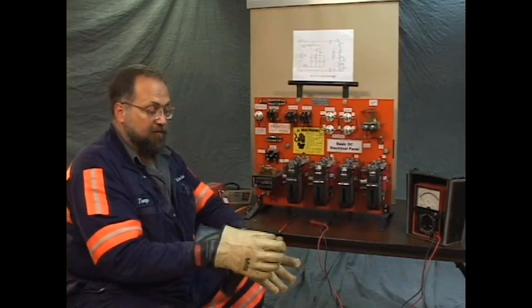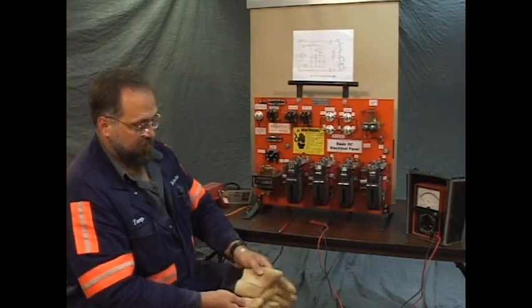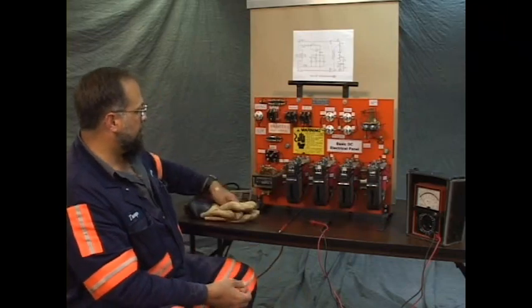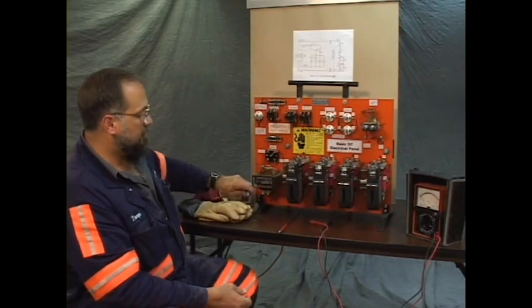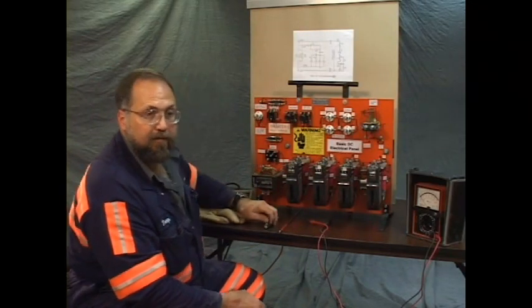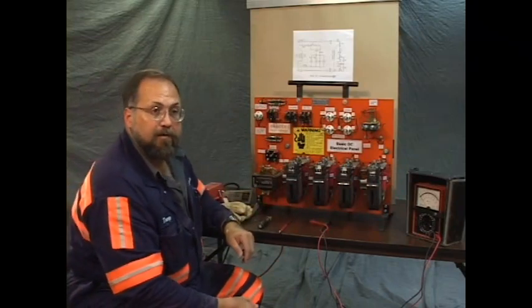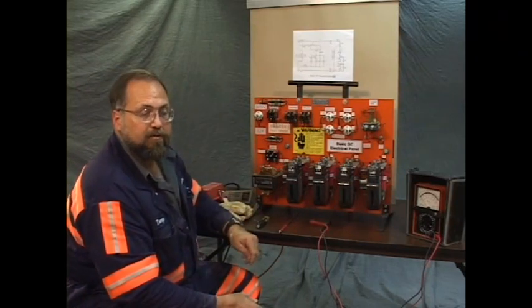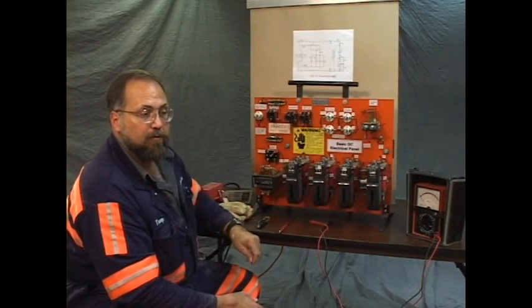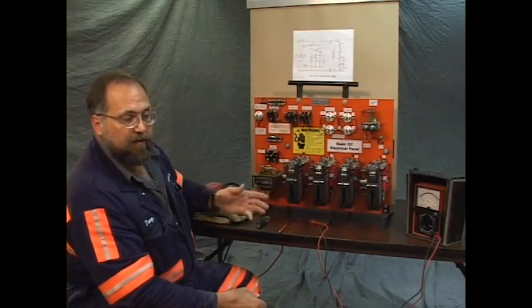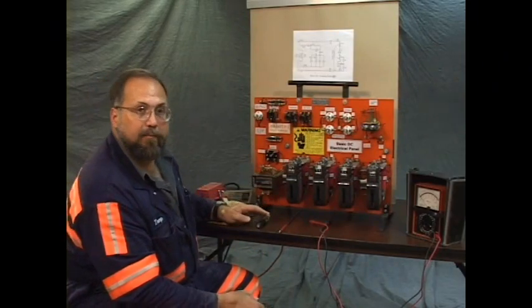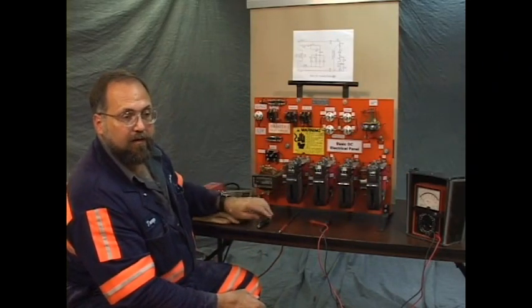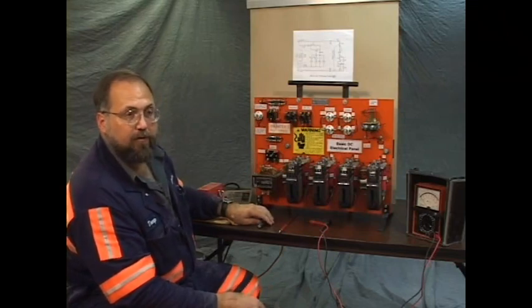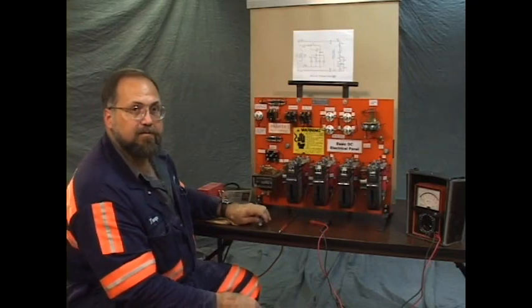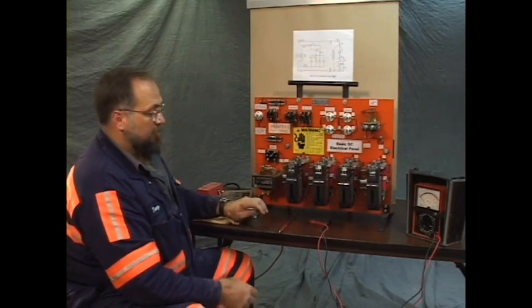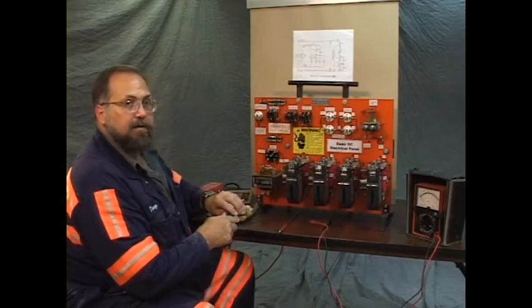It's to be noted that the lock and tag operation is a good deal easier here in training than it is in real life. It takes a good deal of discipline to do this correctly if you have to walk a couple of hundred feet, sometimes in poor conditions, bent over or in wet conditions, to go take a cat head out of the power source and apply a lock and tag and then go back to your work. But that discipline's necessary to stay safe, stay healthy.